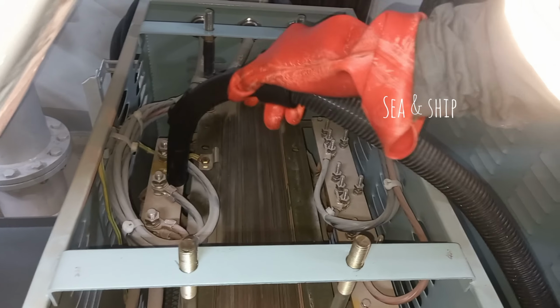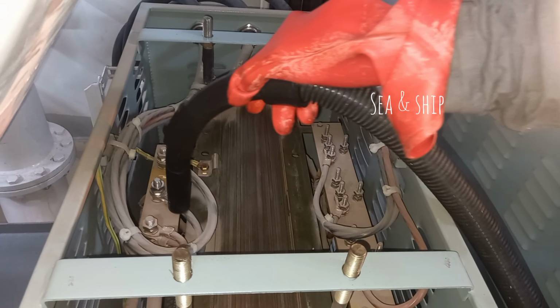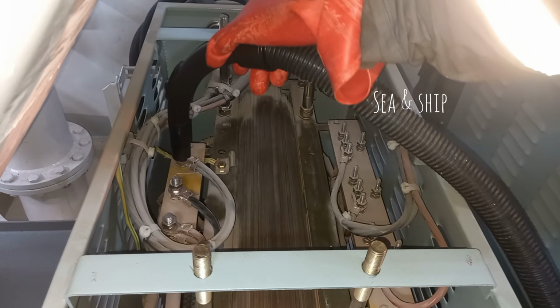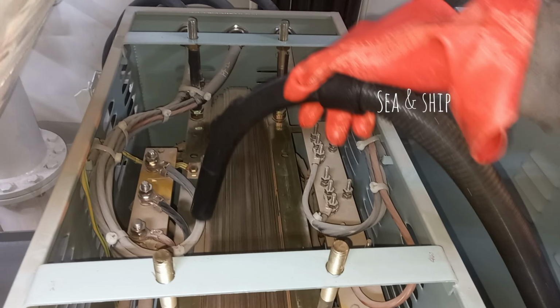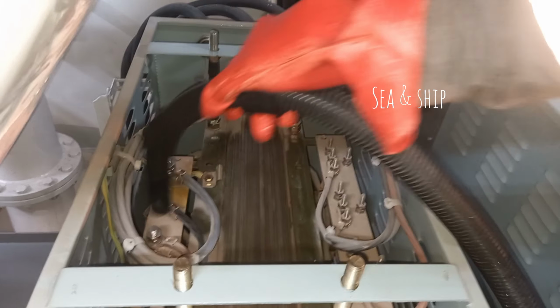Next, inspect insulation condition and, if possible, perform an insulation resistance test using a megger. Also ensure the cooling system is working properly by checking fans and airflow passages are clear.